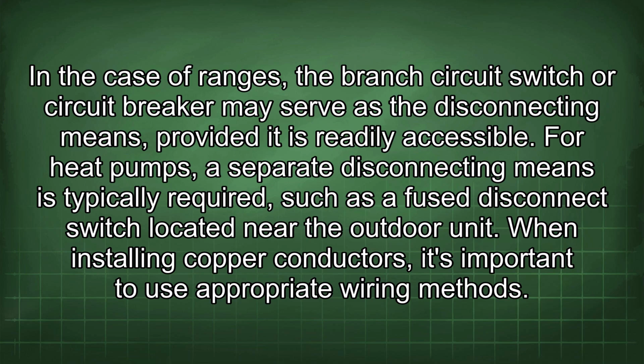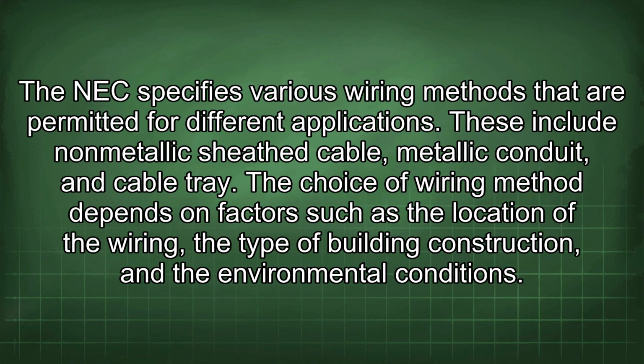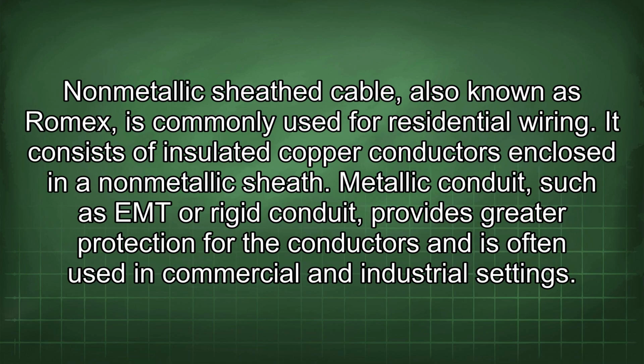When installing copper conductors, it's important to use appropriate wiring methods. The NEC specifies various wiring methods that are permitted for different applications. These include non-metallic sheathed cable, metallic conduit, and cable tray. The choice of wiring method depends on factors such as the location of the wiring, the type of building construction, and the environmental conditions. Non-metallic sheathed cable, also known as Romex, is commonly used for residential wiring. It consists of insulated copper conductors enclosed in a non-metallic sheath.